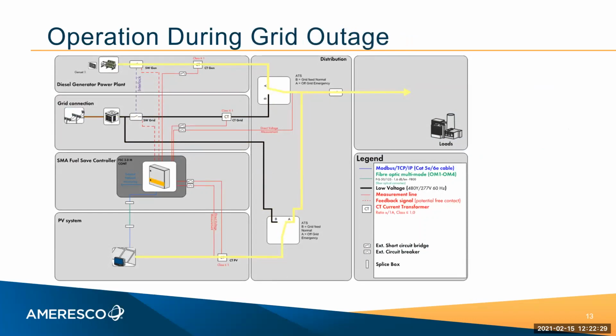So the big change here is that the active power yellow line is now routed, rather than being routed over towards the grid, it's routed up behind the second ATS, which is the top ATS in the distribution section. And now the generator is being run. So the thing to note here is that because this was a front of the meter system, during a grid outage the first thing that would happen was the solar array would be disconnected from the building, and then it would not operate.